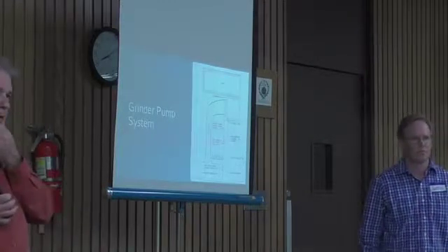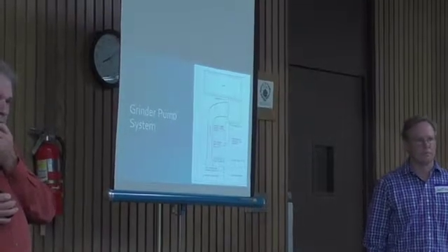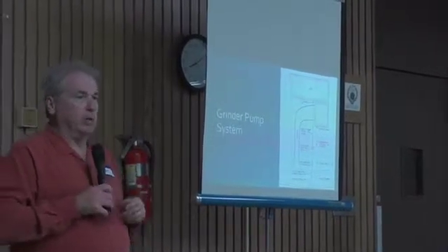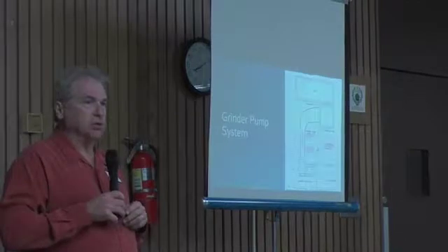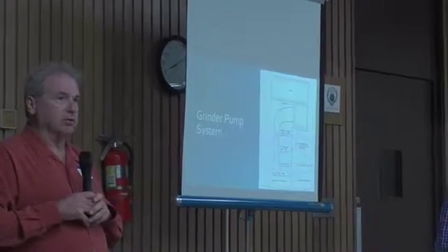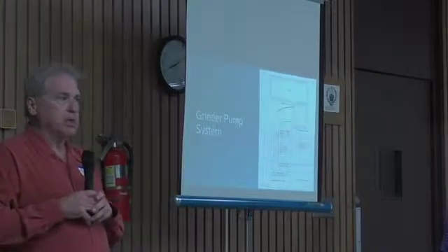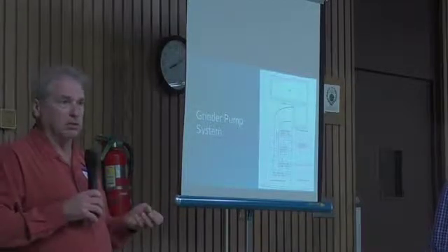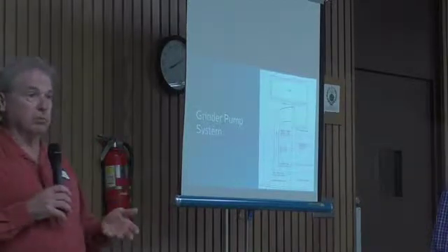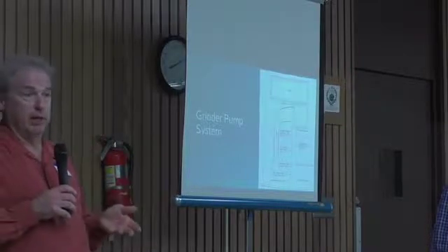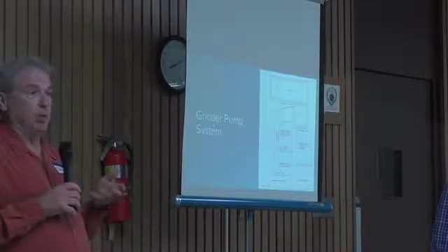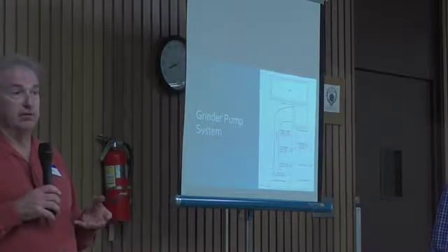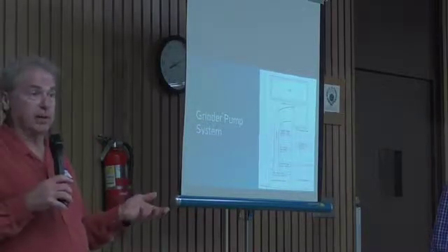So did you look at a vermifiltration system? We encountered that technology with another client of ours, and we looked into that. That system is more geared towards home scale and small commercial scale, and it wouldn't produce the water quality objectives that the state has, even if we applied it in a large scale like this.